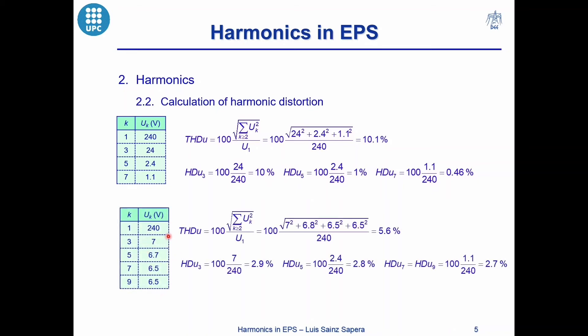Now imagine the following harmonic spectrum: the individual harmonic distortions are all below 5%, so they show that the level of each harmonic is acceptable. But the total harmonic distortion indicates that we have a globally distorted waveform. This is due to the contribution of each harmonic. As a conclusion, we can have a distorted waveform due to a specific harmonic or due to the combined contribution of all harmonics.